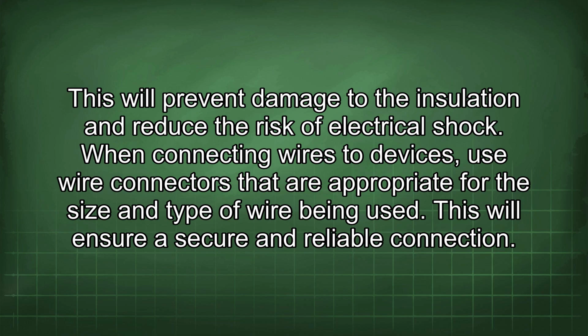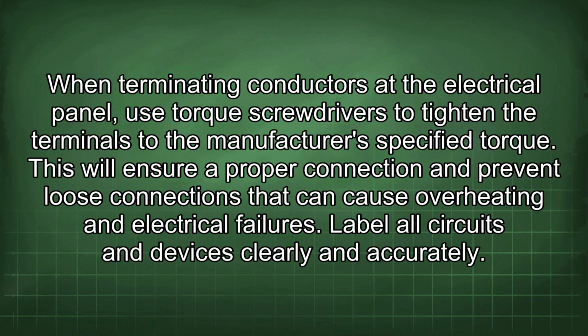When connecting wires to devices, use wire connectors that are appropriate for the size and type of wire being used. This will ensure a secure and reliable connection. When terminating conductors at the electrical panel, use torque screwdrivers to tighten the terminals to the manufacturer's specified torque. This will ensure a proper connection and prevent loose connections that can cause overheating and electrical failures.